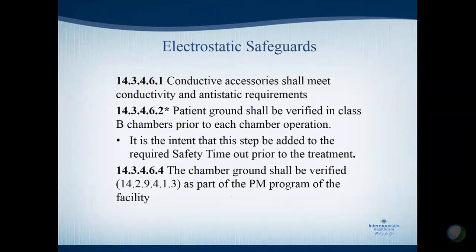And that intent, of course, is not in the code, but code language now requires that we check patients in monoplace chambers before the treatment. And then as far as maintenance, in the inspecting, testing, and maintenance section, we have the chamber ground being verified as part of the preventative maintenance for that facility. So there's two separate steps that are happening there.